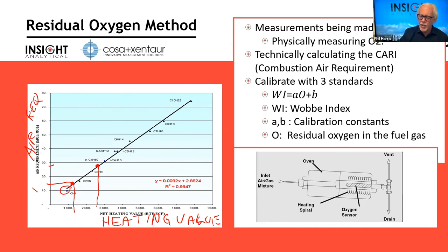The thing we're showing down here is just how the oxygen analyzer works. So there's a zirconia oxygen analyzer. It heats up a piece of ceramic zirconium, with air on one side of it and the thing we want to measure on the other, and it develops a voltage across it. So it's a fairly simple measurement. By physically measuring the oxygen, we end up with a measurement of this combustion air requirement.